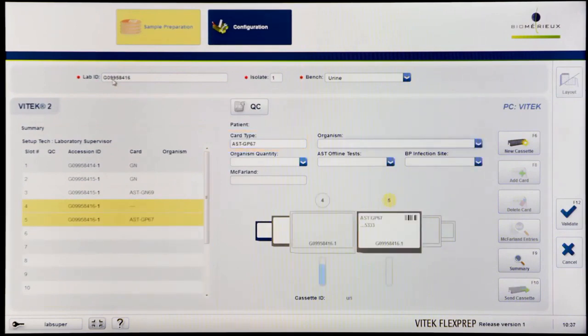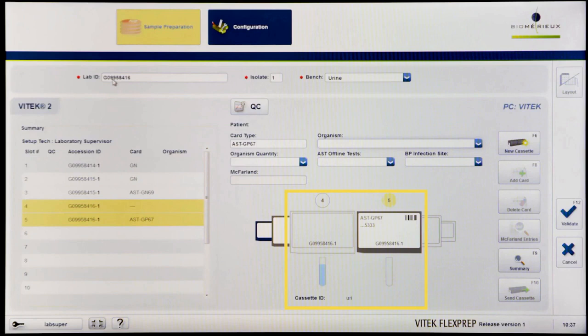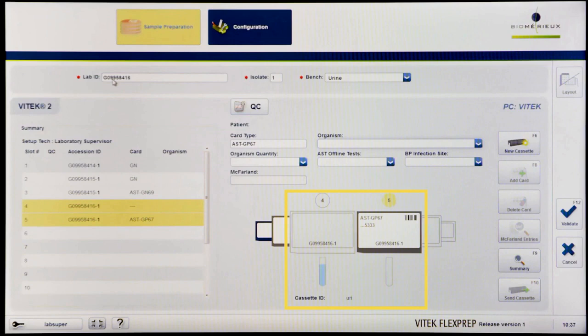Once the card type is entered, a graphic of the isolate will display. Because Automatic Dilution Mode is enabled, FlexPrep utilizes two slots, one for an organism suspension and one for an AST suspension. The organism suspension is indicated by a full tube. The AST suspension is indicated by an empty tube. In Automatic Dilution Mode, the VITEK 2 instrument will add saline to an empty AST tube and will pipette the proper amount of the organism suspension for an AST dilution. Be sure to place an empty tube in the cassette in the slot indicated.